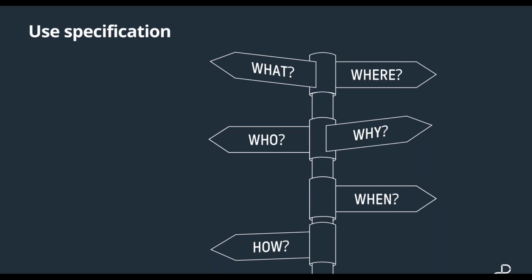It creates a background of knowledge about who the users are, what their capabilities are, and what other aspects of their profiles relate to how they can interface with the product. It talks about the environment where that product might be. Is it a home environment? Is it a hospital environment? Is it a surgical environment? Matching up who the users are, whether it's patients, nurses, doctors, surgeons, and where the product is, provides very important context for the usability engineering process.